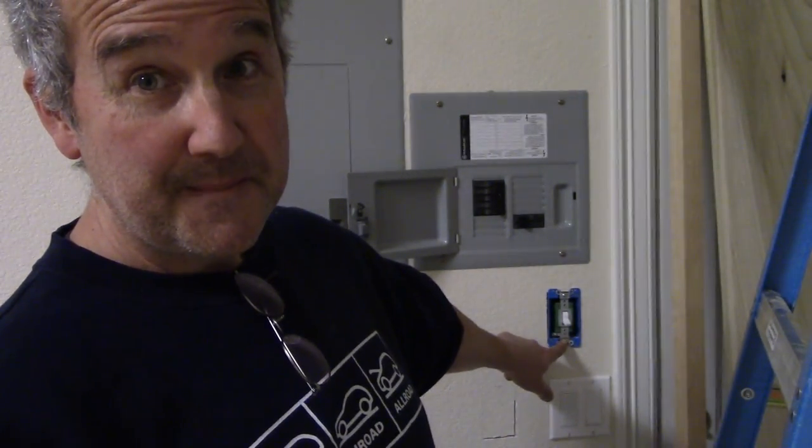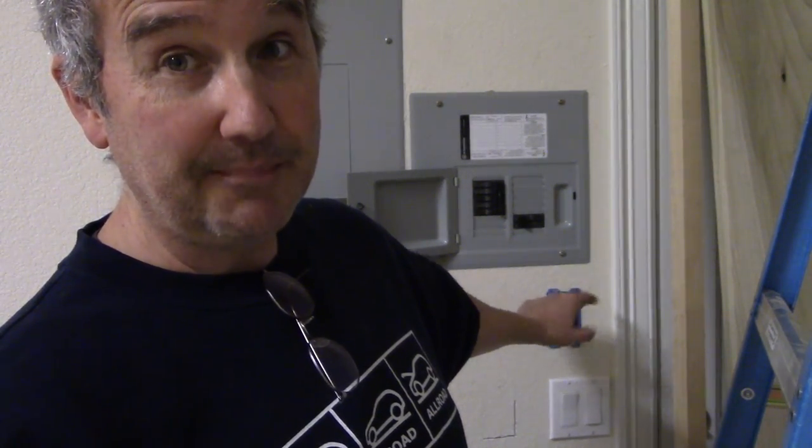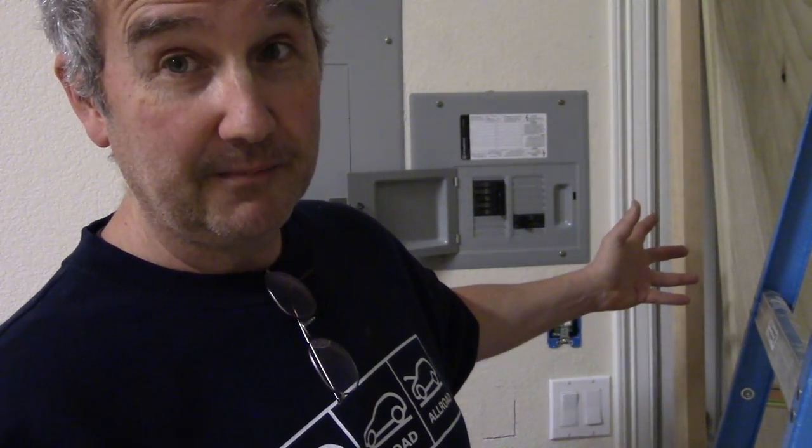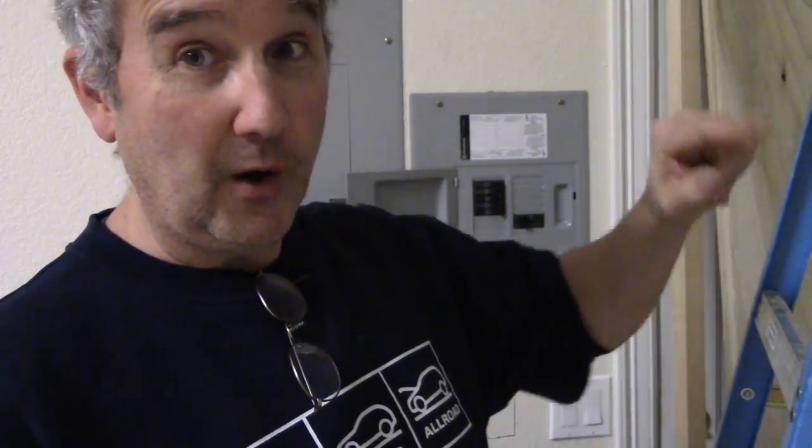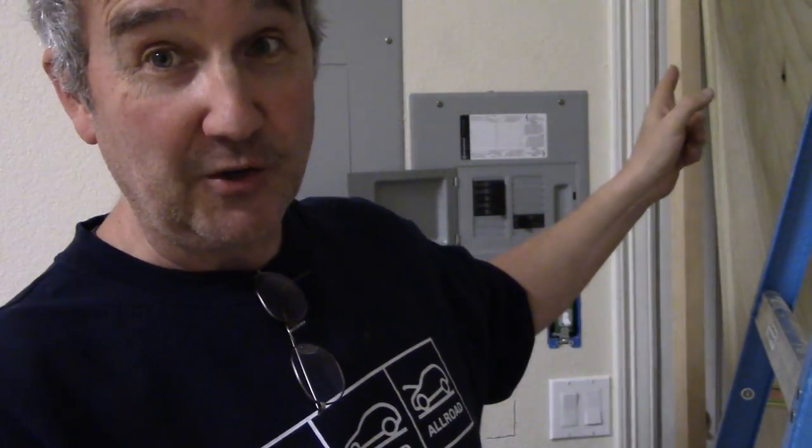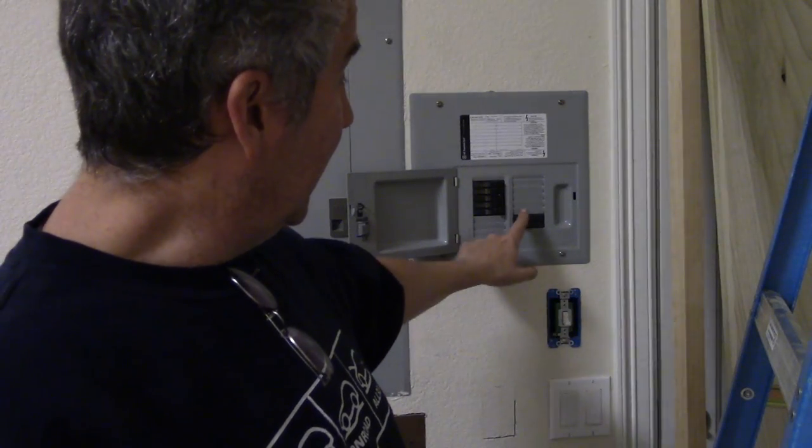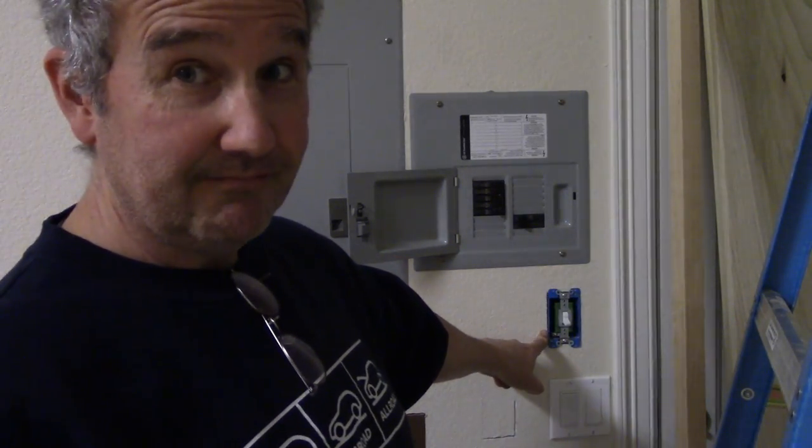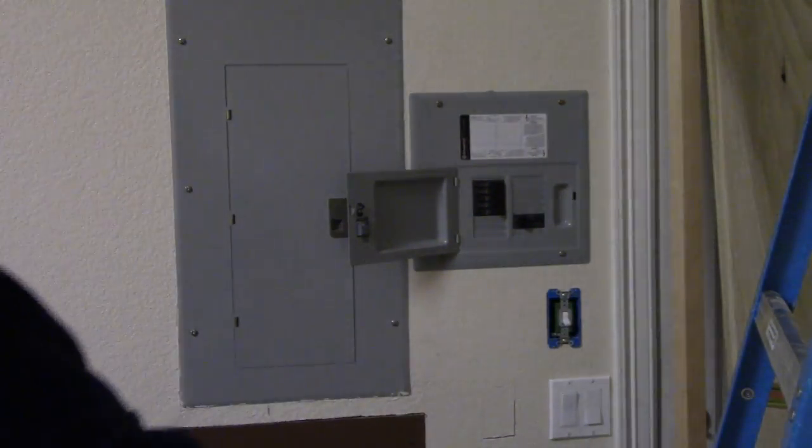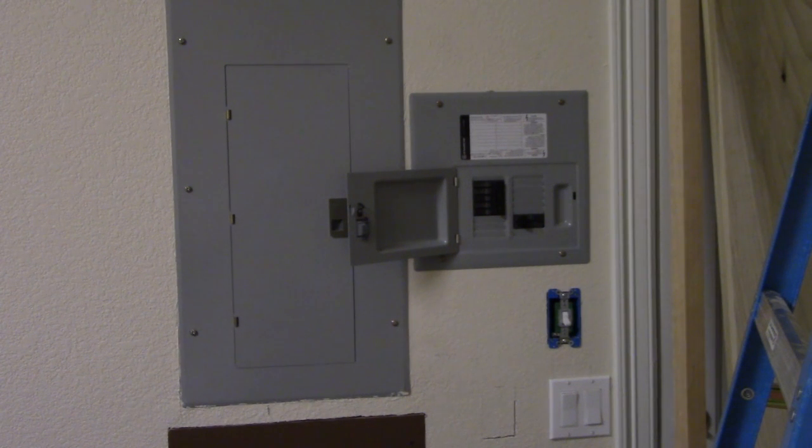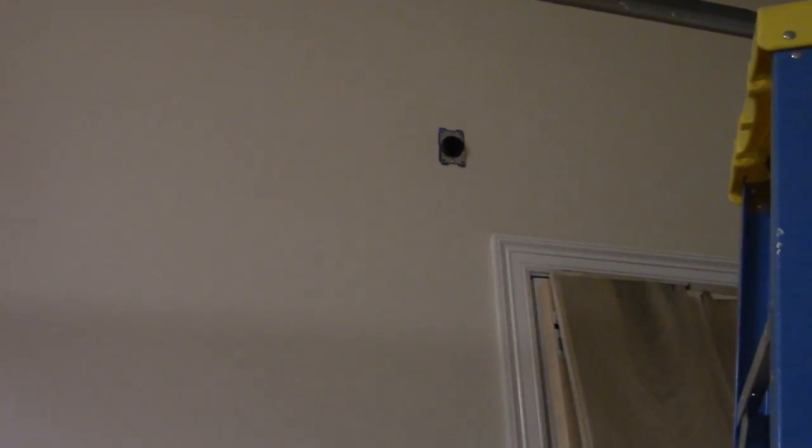There's two poles on the bottom, and those are the line-in, and then the two poles on the top are the line-out. Both the white and the black go parallel to each other through the switch, rather than just having the neutral going all the way to the end product like in 120 where you're just breaking the hot lead. This one, you're breaking both hot leads. So from here to here we have a connection, and then from here up there.